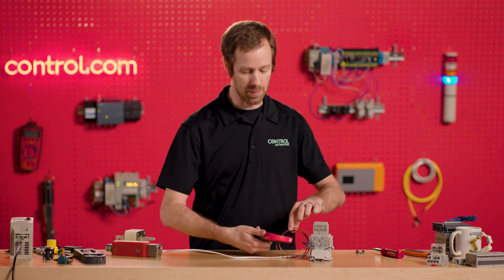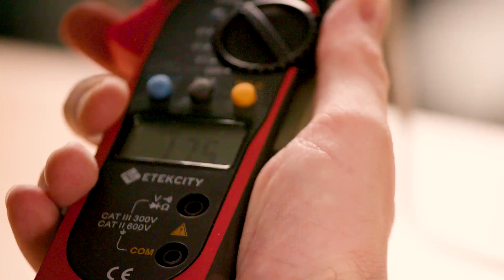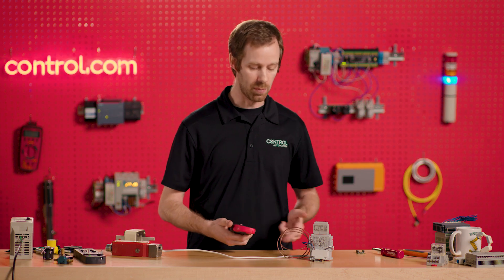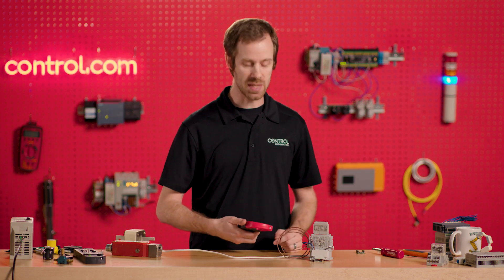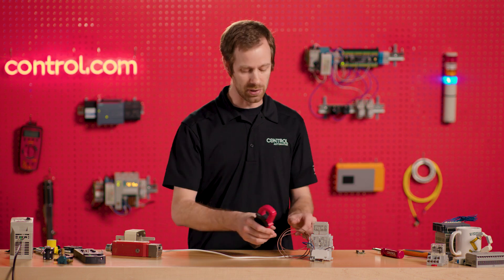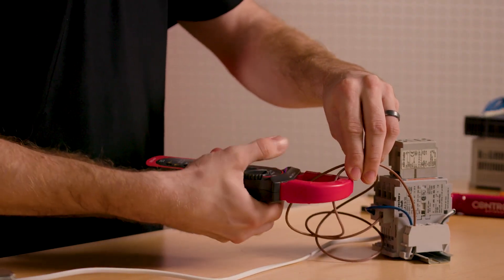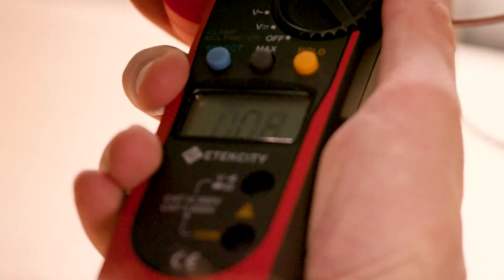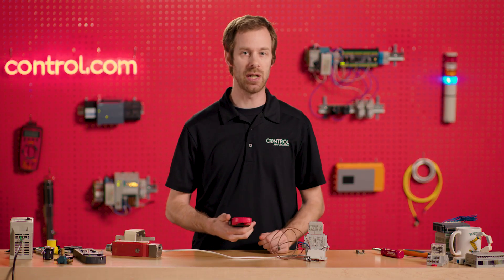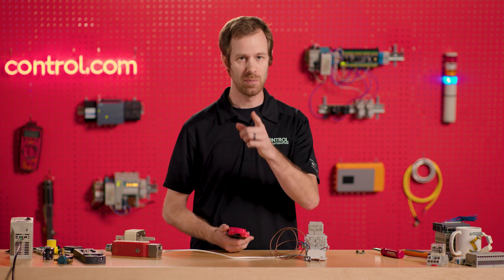One thing that I do have to remember, no matter how many strands I'm using, is that I need to divide the number that I see on the screen by the number of strands. Because when I coil it multiple times, the current has been multiplied by the number of coils. But we do have to be careful, because if we put the coil on the wrong direction, they will cancel each other out and will have a false reading. So this is a handy trick to know if you have spare wire and need a little bit more accurate measurement. Andy, back to you.